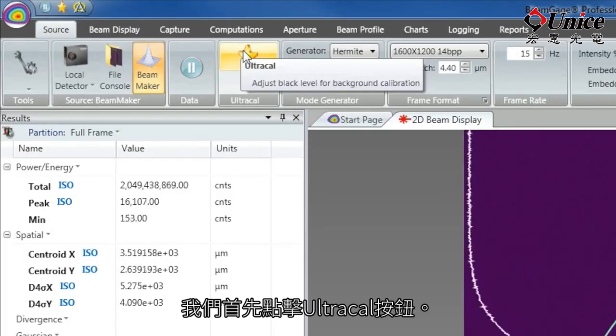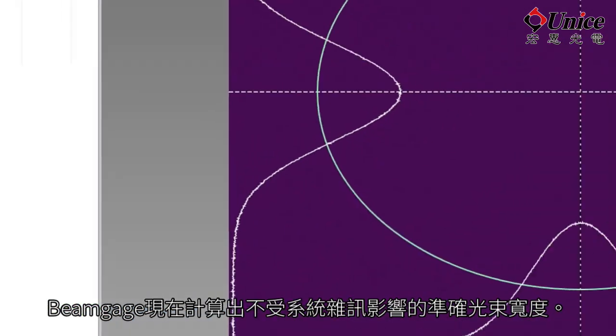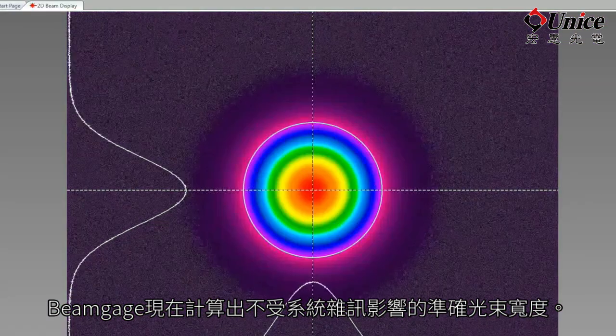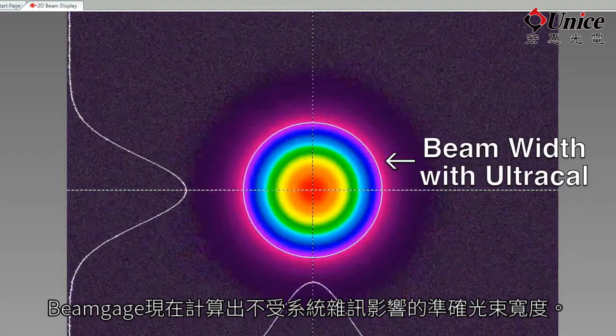We start by clicking the Ultracal button. BeamMaker blocks our beam, then collects sample data and calculates the baseline with the noise removed from each pixel. BeamGage now calculates the accurate beam width without system noise.